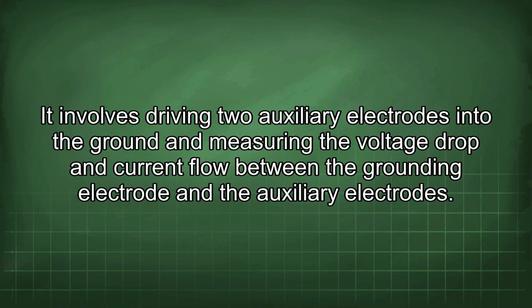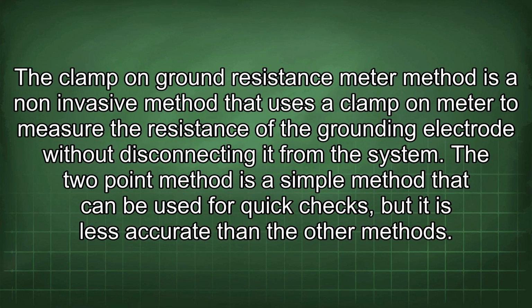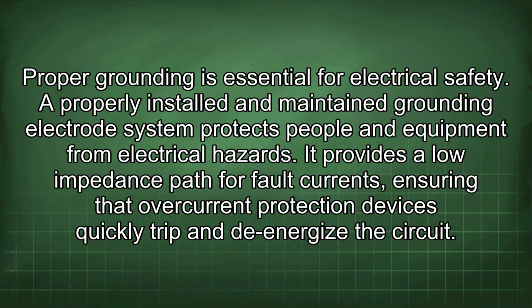It involves driving two auxiliary electrodes into the ground and measuring the voltage drop and current flow between the grounding electrode and the auxiliary electrodes. The clamp-on ground resistance meter method is a non-invasive method that uses a clamp-on meter to measure the resistance of the grounding electrode without disconnecting it from the system. The 2-point method is a simple method that can be used for quick checks, but it is less accurate than the other methods. Proper grounding is essential for electrical safety.